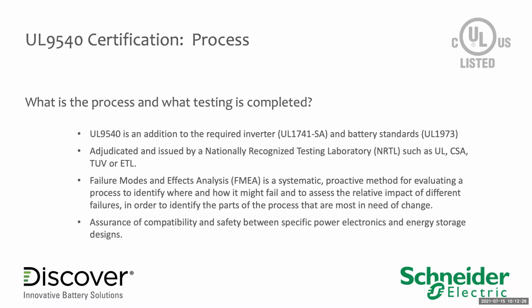If there's a dead short on the DC bus, what happens to the inverter? What happens to the batteries, and how does it handle it? Is it safe in that combination? If there's an AC short, a runaway control board, a lost cap bank, or if our FET board or supplementary protection doesn't work, what's the worst case, how does it happen, and how do those two products react together? Are there fail-safes built in such that they're safe if one of those items happens?